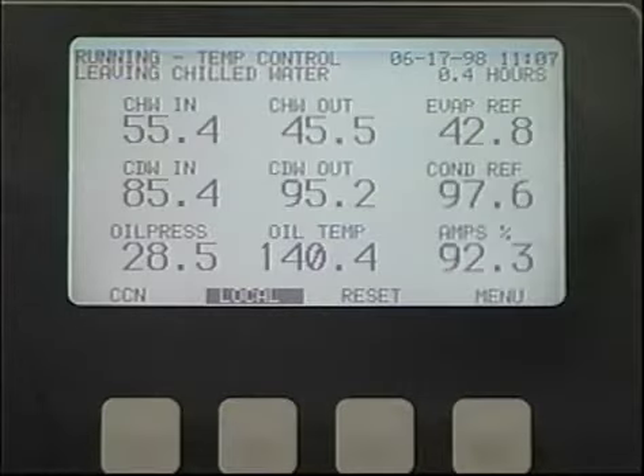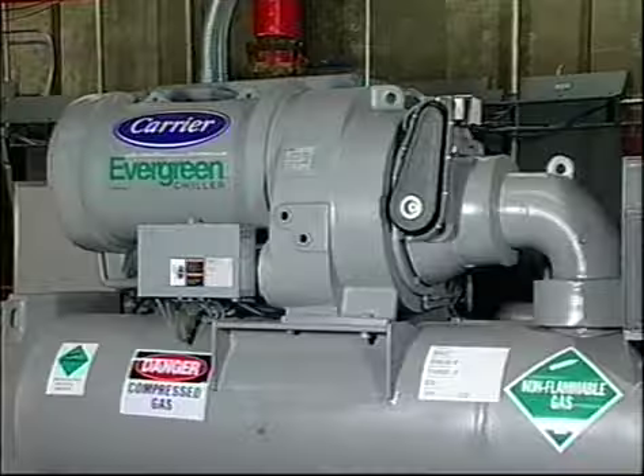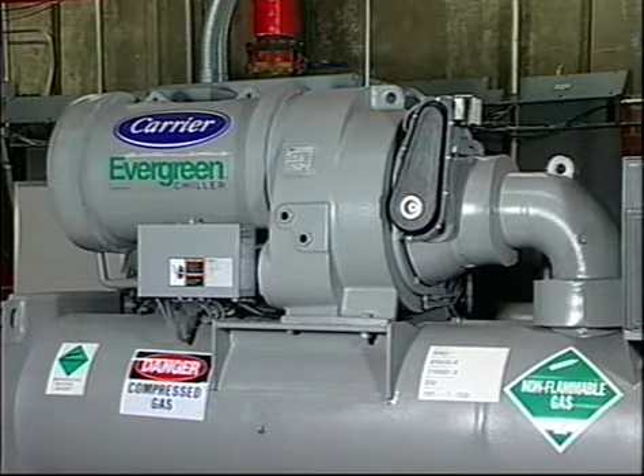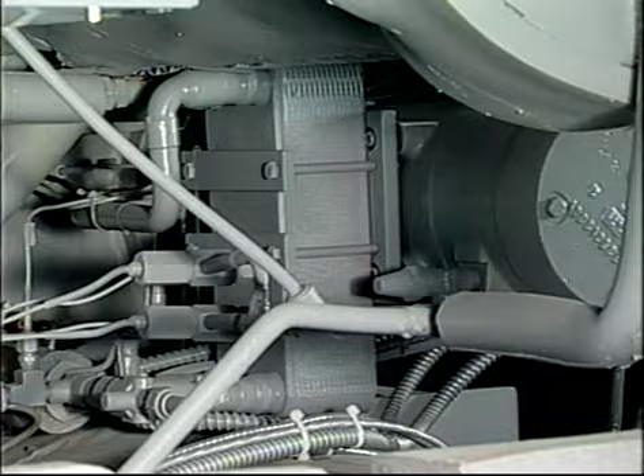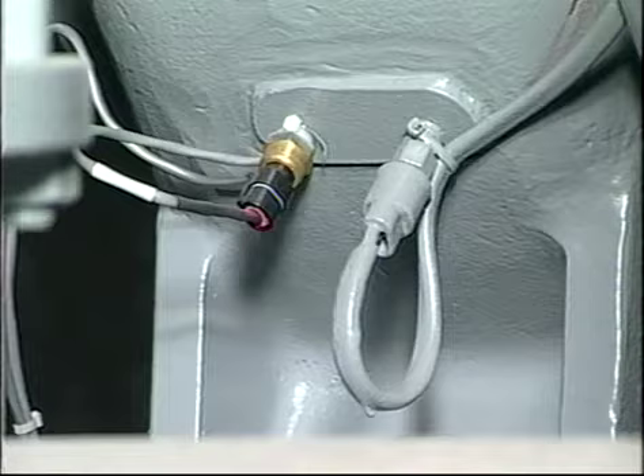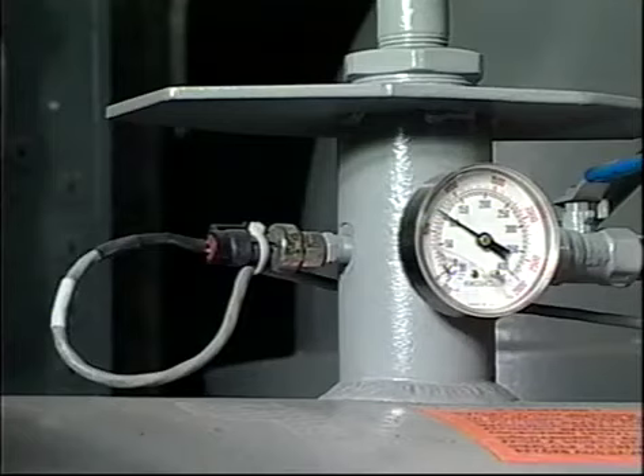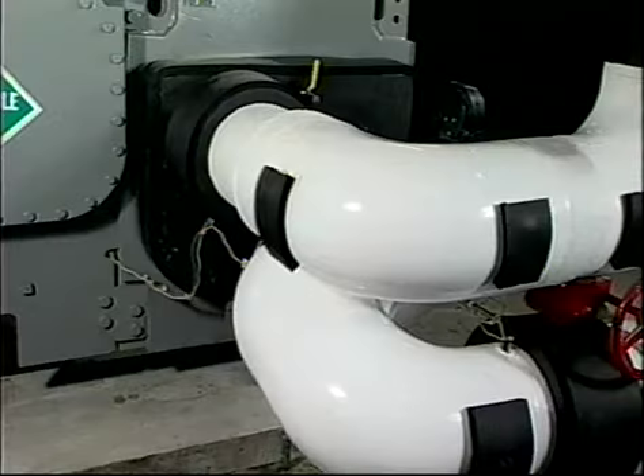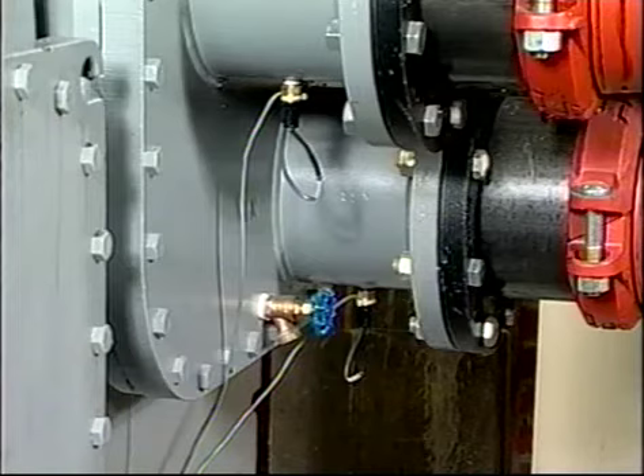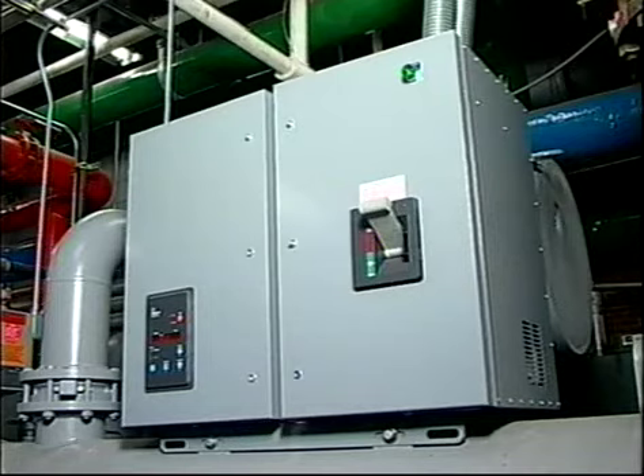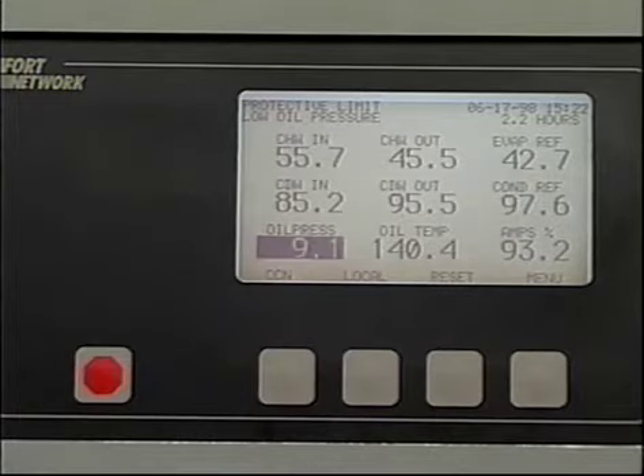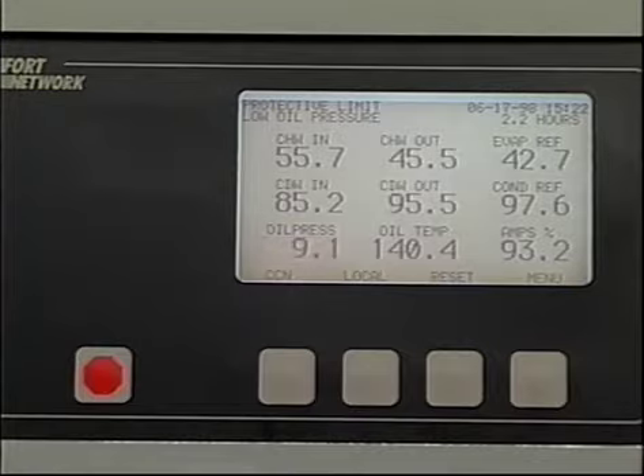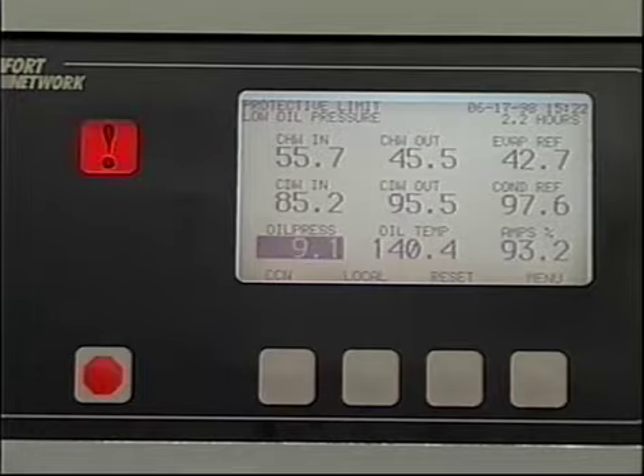Your chiller is well protected by the PIC controls. Here are just some of the points that are monitored by the controls: compressor motor temperature, bearing temperature, oil temperature, oil pressure, discharge gas temperature, cooler pressure and condenser pressure, water temperatures entering and leaving the cooler and entering and leaving the condenser, and compressor motor amps and volts. If any of these points should go beyond safe operating limits, an alert or alarm is generated, and the chiller is automatically shut down if the condition becomes serious. The controls even automatically check the temperature and pressure sensors to ensure that the sensors are not faulty.